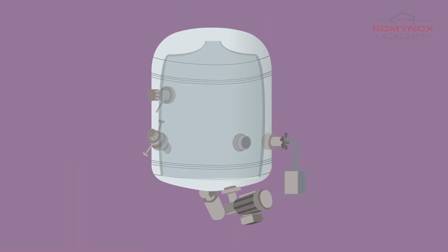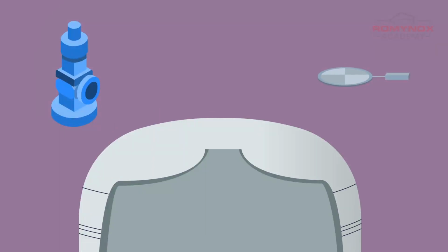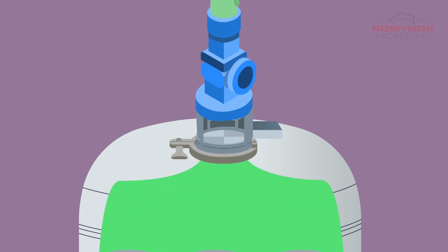If prolonged exposure of the environment to the medium is to be avoided, a combination of a spring-loaded device and a bursting disc may be used. A bursting disc is fitted, on top of which a safety valve is installed and adjusted to a slightly lower pressure limit. This ensures that the system remains closed even after an incident. The drawback of this solution is the space between the safety valve and the bursting disc. This area must be ventilated, which can be done with a telltale and pressure indicator.